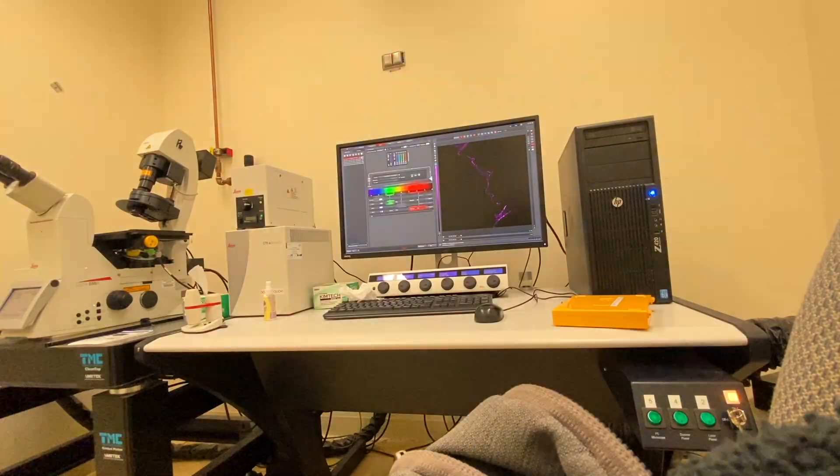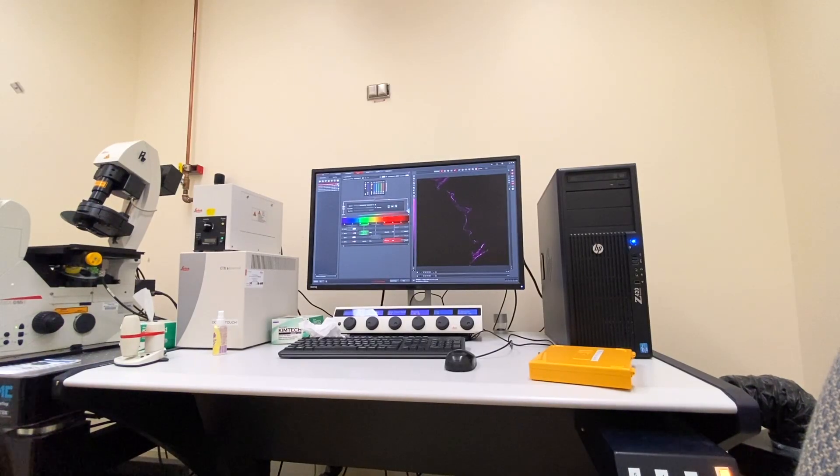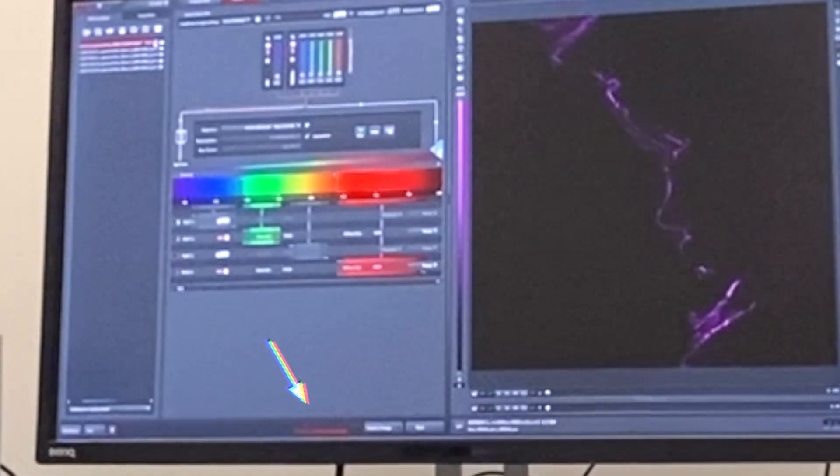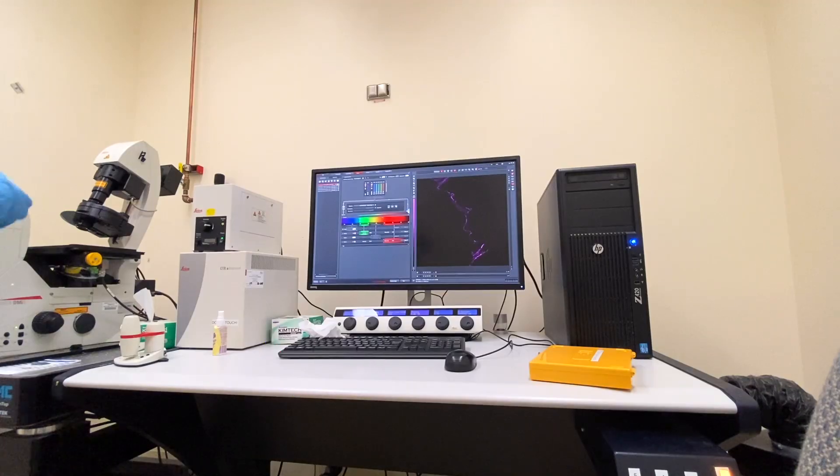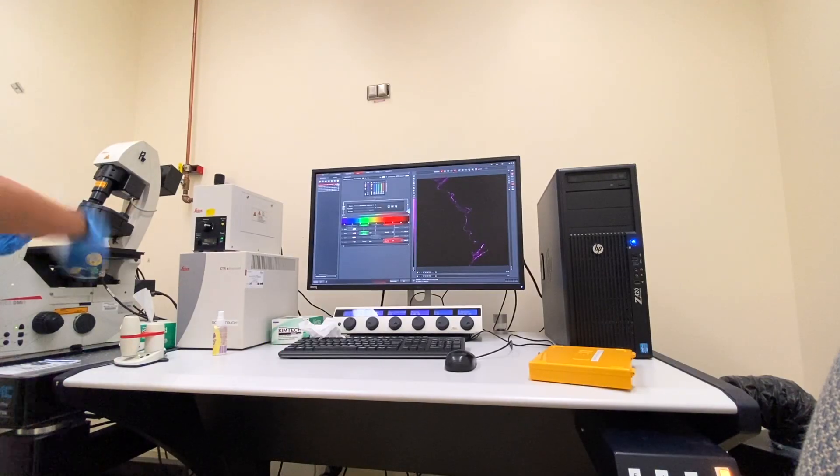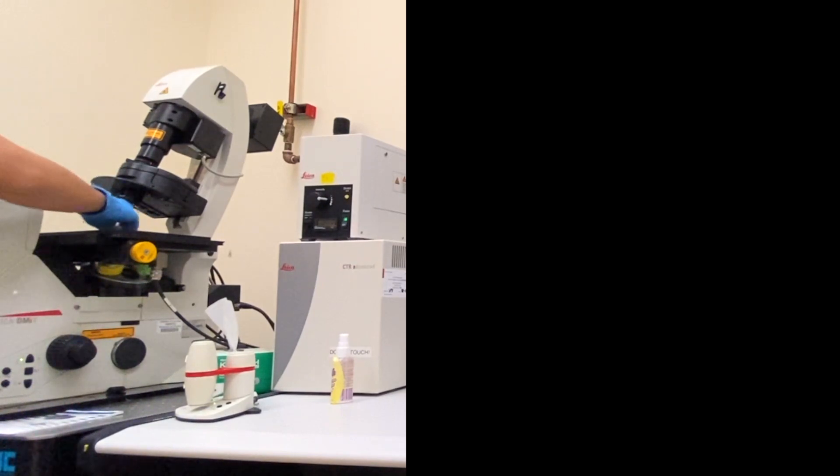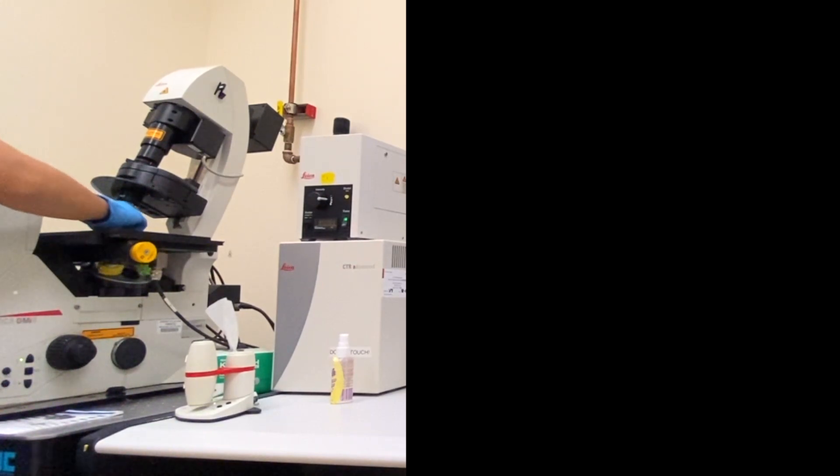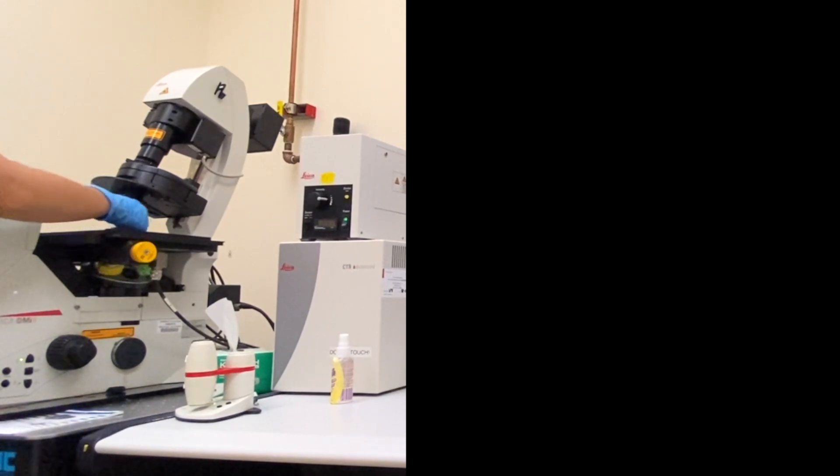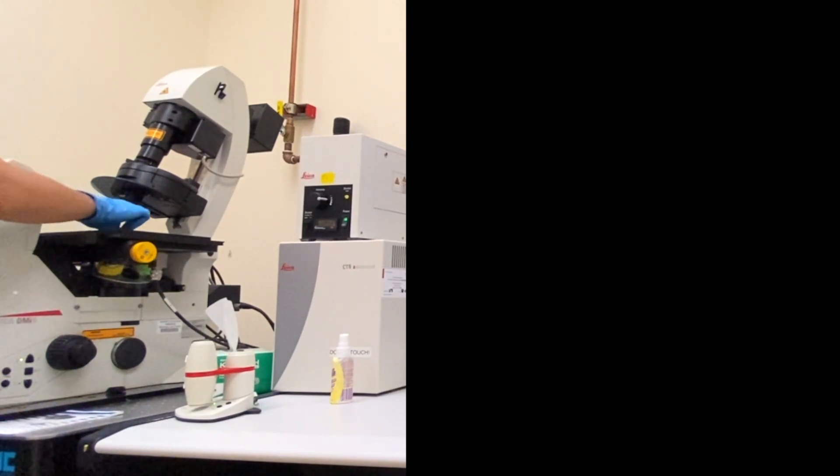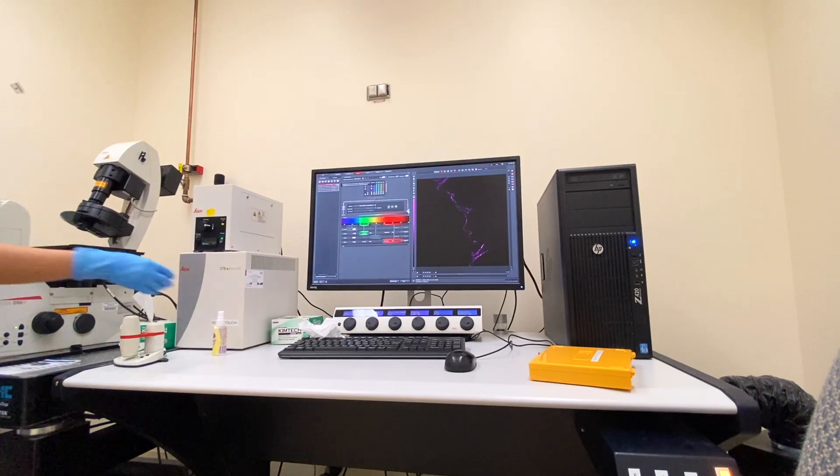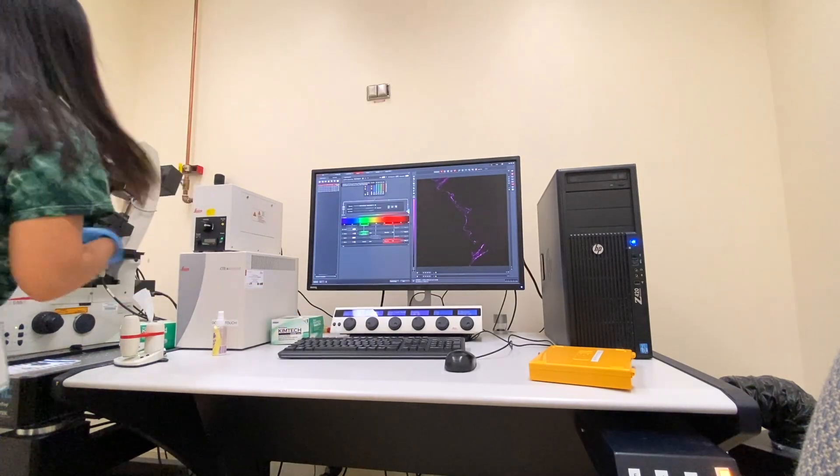Alright, it's time to wrap up and shut down the microscope. With shared and expensive equipment, they must be turned on and off properly. I clean my slides with eyeglass cleaner. Save my files to a shared server. And I also clean the microscope's objective lens. And this is because I used oil with this particular objective, which is needed for certain lenses to get optimal resolution. I clean the microscope area for the next person.